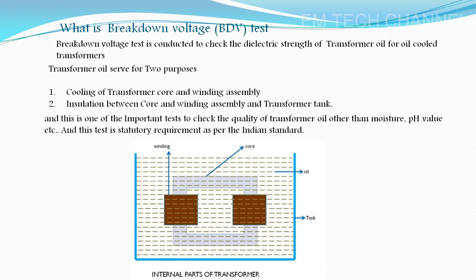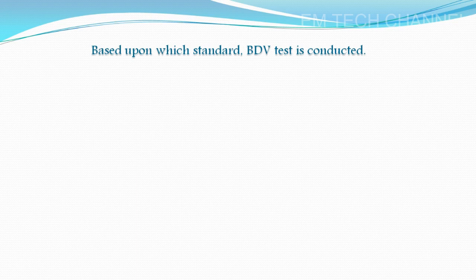And this is a schematic. You can see here the core and winding assembly is placed in the center of the transformer tank and is surrounded with the transformer oil, and this oil serves as cooling for the core and winding assembly as well as an insulator between the core and winding assembly and the tank. The transformer tank is a metal conductor, and the core and winding assembly is also a metal conductor, and in between, the transformer oil acts as an insulator. Any insulator placed between two conducting materials is called a dielectric. We are going to check this dielectric quality of the transformer oil, and based upon which standard this breakdown voltage test is carried out.